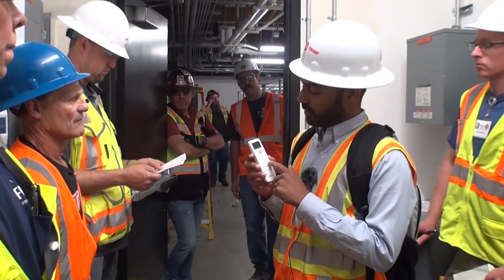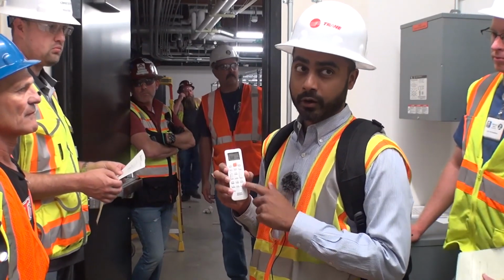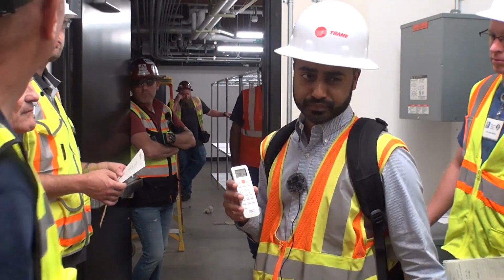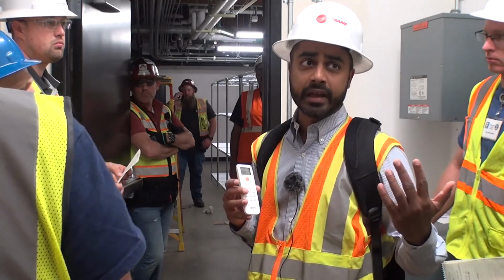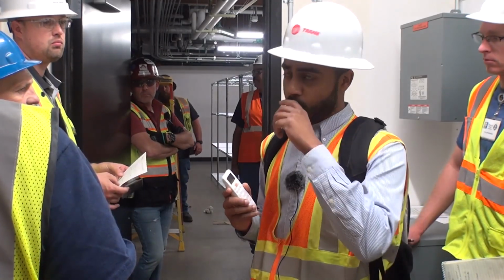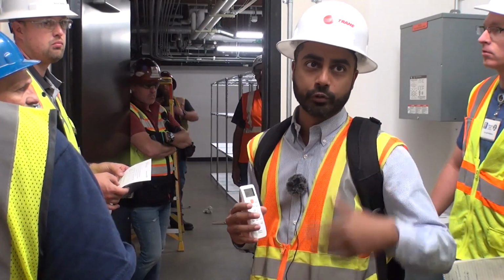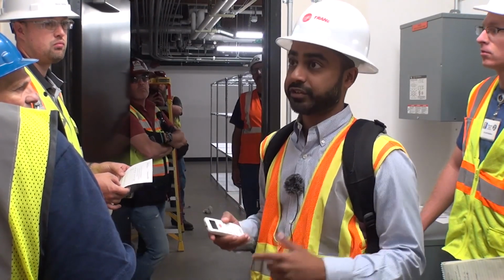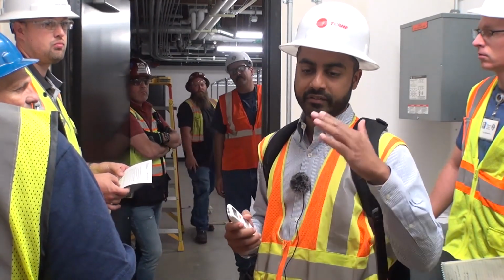Like I said, fan speed settings have been set to auto, so they can actually modulate the room speed. Originally they were just left on high fan speed, and what ended up happening is it overcooled the rooms—the set point was 68, but it was actually 64 in here because the unit doesn't have any ability.